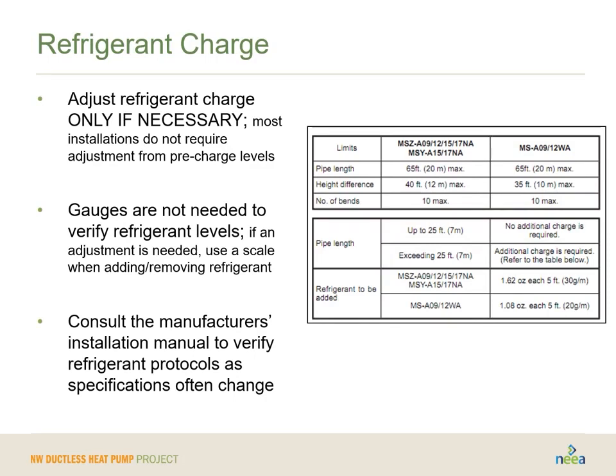Refrigerant charge. Only do this if it's actually necessary. Many or most installations don't actually require adjustments because they come pre-charged. When they're pre-charged, you don't really need gauges to verify the refrigerant levels because, again, they're factory set to work this way. But consult your manufacturer's installation manual and verify that the protocols we're talking about today apply to the equipment that you're installing. And again, make sure you do have your refrigerant handling license if you're going to be doing this work.